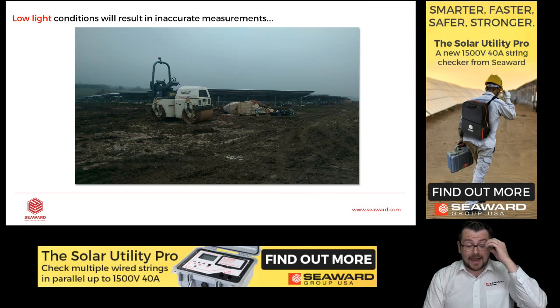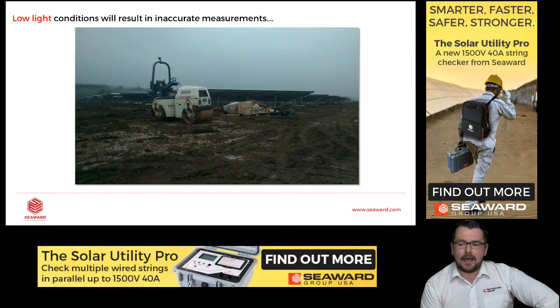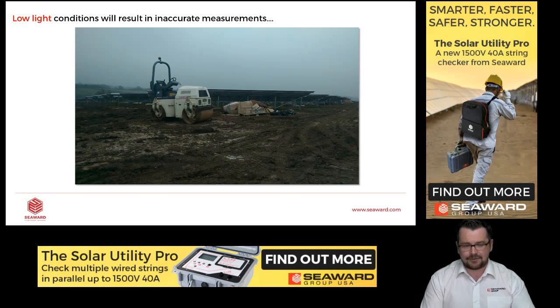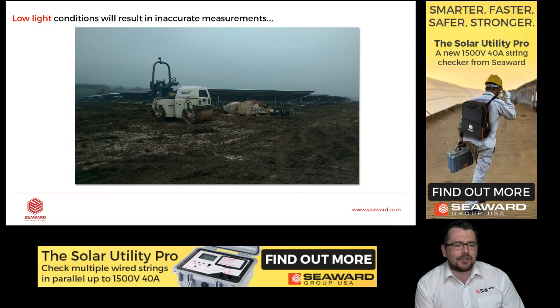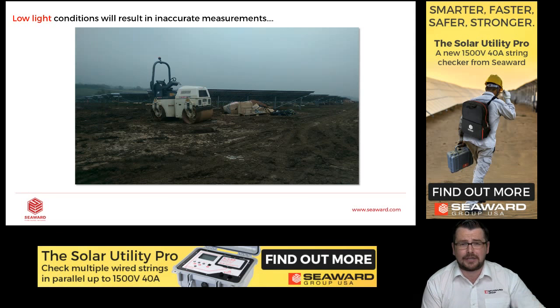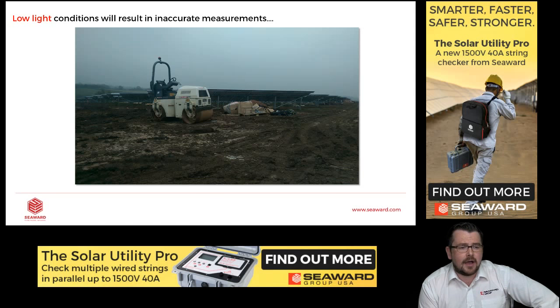As you can probably tell from my accent, I'm originally from the United Kingdom, and I found that testing in my country of birth is quite difficult at times because the irradiance levels are very low, particularly in this time of year. So this was a site in Ludlow in the United Kingdom, and as you can see, I was asked to come out to test this site, and we had to call it off. The trip was wasted because we had below 100 watts per meter squared of irradiance. This picture was taken at about 1 o'clock in the afternoon. So really the sun should have been quite high and we should have had good irradiance. But sometimes geographically that's simply not the case.